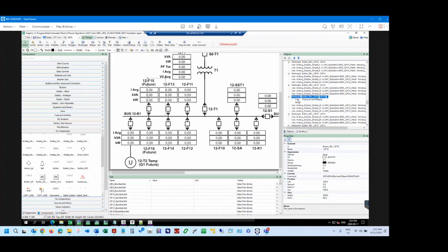There are other buttons that look more like a nice button, but those are more visual, and I wanted this to be invisible, so that's why I used a rectangle. Another thing about rectangles, they work great for status objects. For example, if you wanted to just have a small square that turns on or off or becomes visible or invisible based on an alarm condition, red, green, changing color, simple like that. We have other objects that are just built off of a rectangle. Super simple.